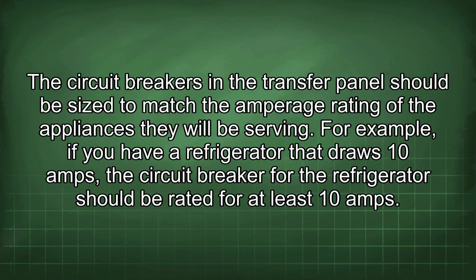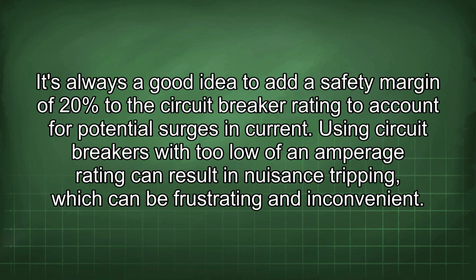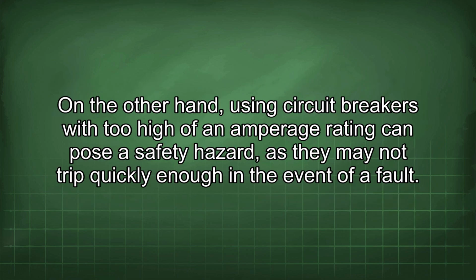The circuit breakers in the transfer panel should be sized to match the amperage rating of the appliances they will be serving. For example, if you have a refrigerator that draws 10 amps, the circuit breaker for the refrigerator should be rated for at least 10 amps. It's always a good idea to add a safety margin of 20% to the circuit breaker rating to account for potential surges in current. Using circuit breakers with too low of an amperage rating can result in nuisance tripping, which can be frustrating and inconvenient. On the other hand, using circuit breakers with too high of an amperage rating can pose a safety hazard, as they may not trip quickly enough in the event of a fault.